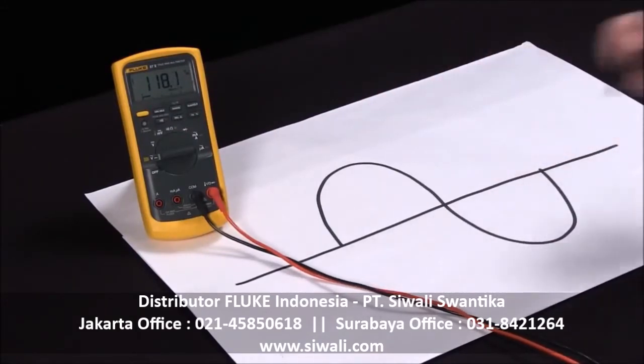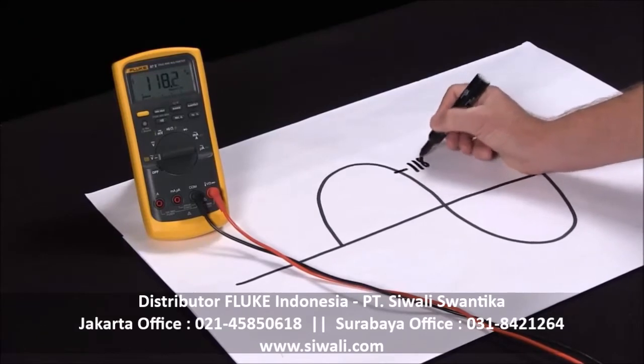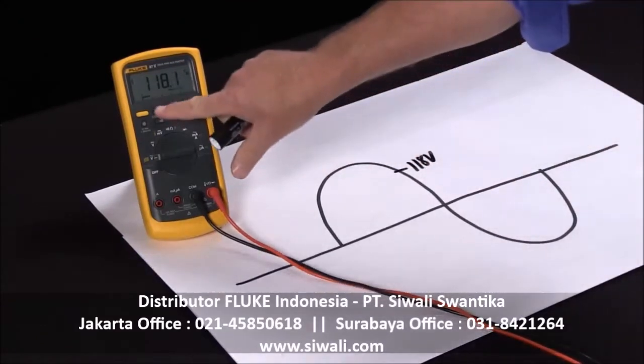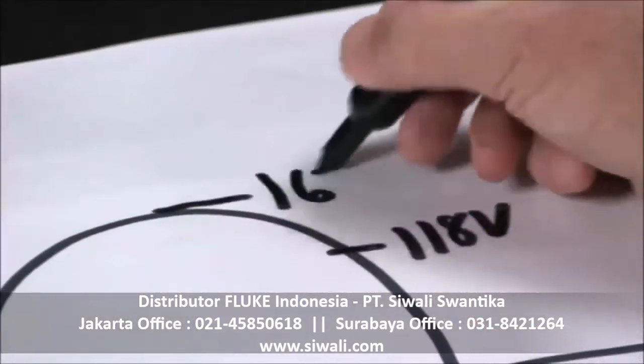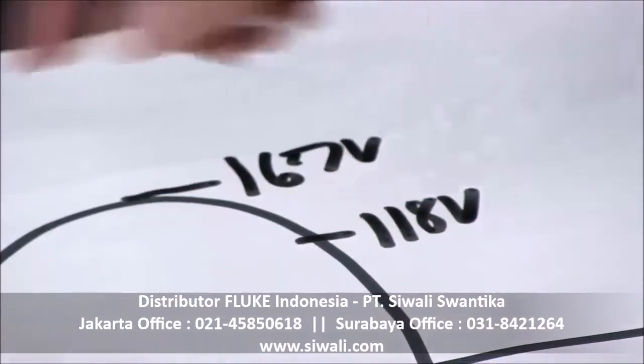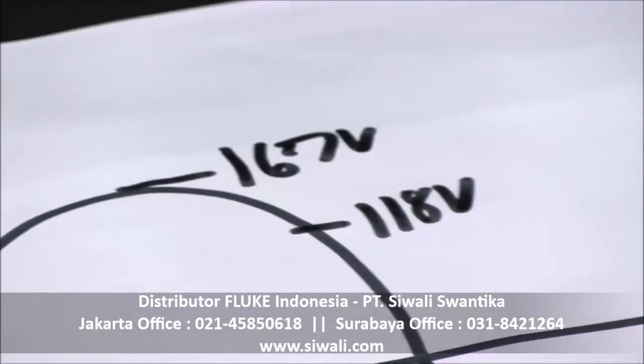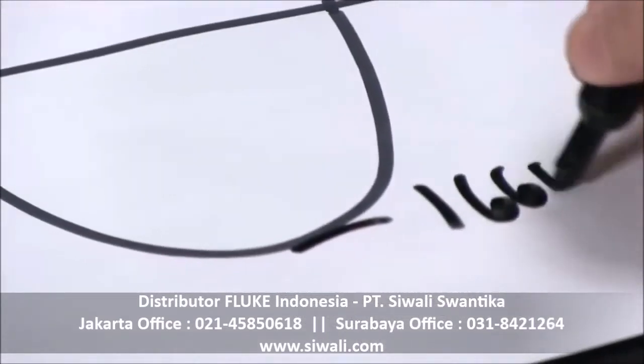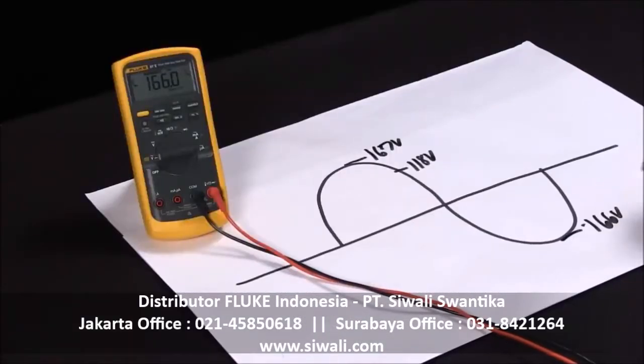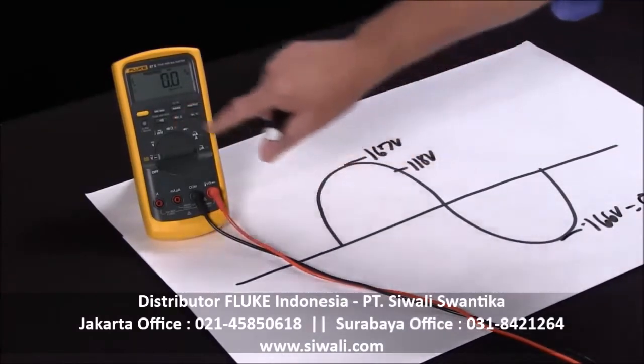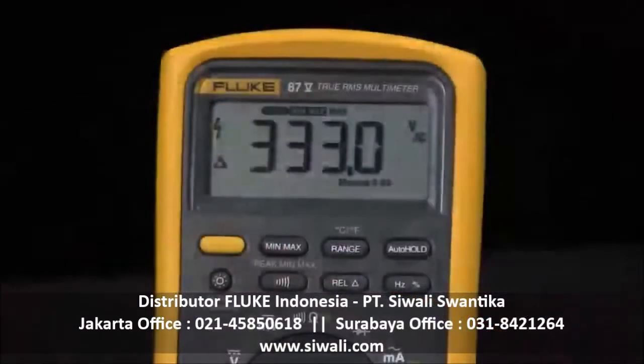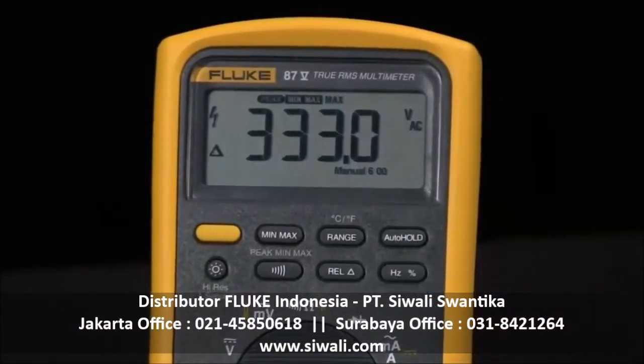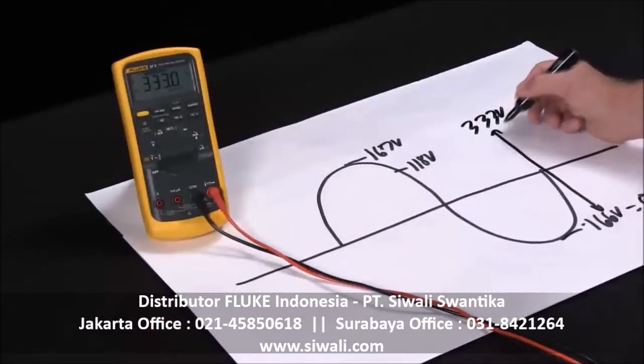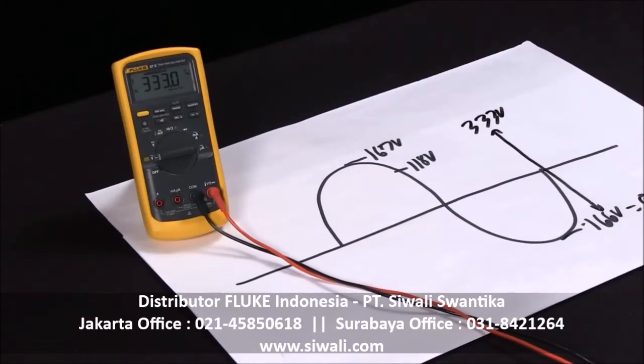Right now, we're looking at 118 volts, which is the RMS value of this sine wave. If I hit the peak min max mode, now with the fast peak mode, I can actually measure the peak at 167 volts. And with min max, I can hit that, and now I get the negative 166 volts. Where the relative mode comes in is I can now make this negative a 0. So if I hit relative, that becomes 0. And now I'm measuring the peak to peak of 330 volts of this sine wave by using a combination of the fast min max and the relative mode.